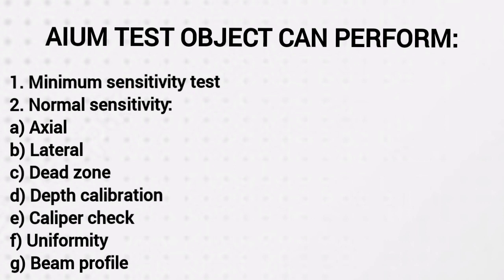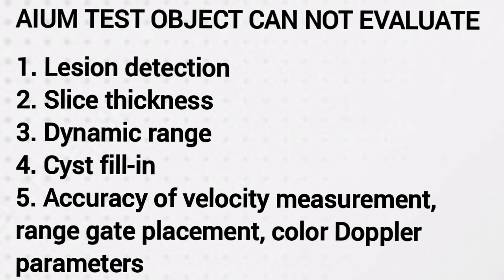So the AIUM test object does not provide the attenuation and or scattering properties of tissue. So it cannot be used to test tissue characteristics or grayscale information. AIUM test object cannot evaluate or test for the following: lesion detection, also called detail resolution or grayscale. It cannot evaluate slice thickness, dynamic range, cyst fill in, accuracy of velocity measurement, range gate placement, and color Doppler parameters. It doesn't do that.